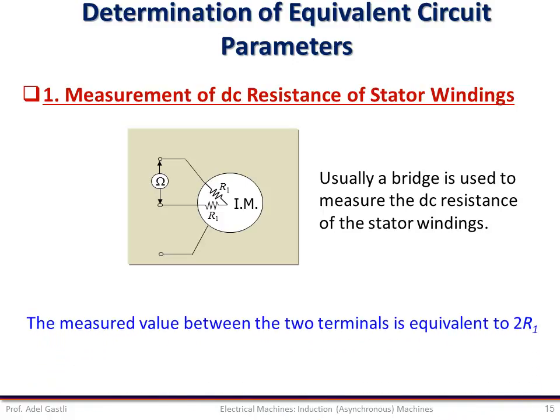The measured value between the two terminals is equivalent to twice the stator resistance R1. However, since the measured resistance is a DC equivalent resistance while the winding is subject to AC current, it is preferable to use a correction factor to find an approximate AC value of the stator resistance, accounting for the skin effect under alternating current. Usually at 50 or 60 Hz the difference is not significant, but for high frequencies a correction factor should be considered. Note that the AC resistance should be higher than the DC resistance.